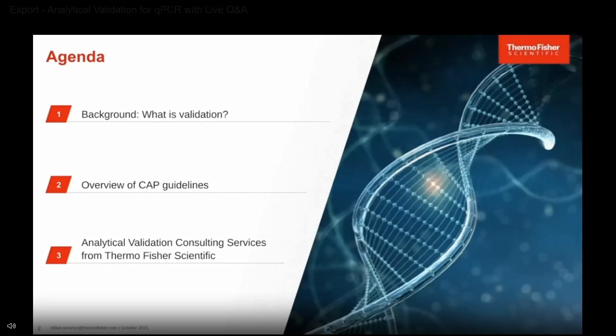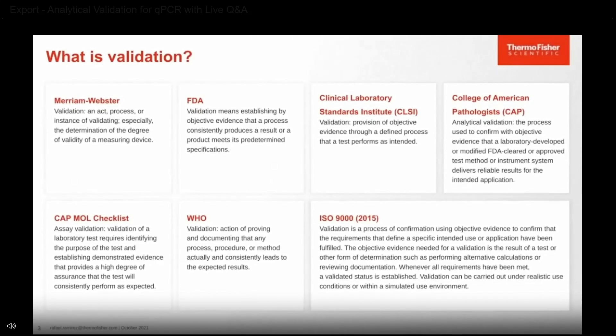Let's talk about what a validation is. There are many different definitions. The FDA states: a validation means establishing by objective evidence that a process consistently produces a result or a product meets its predetermined specifications. The CAP molecular checklist states: a validation requires identifying the purpose of a test and establishing demonstrated evidence providing a high degree of assurance that the test will perform consistently as expected. ISO states: a validation is a process of confirming objective evidence to confirm that the requirements defining a specific intended use or application have been fulfilled.